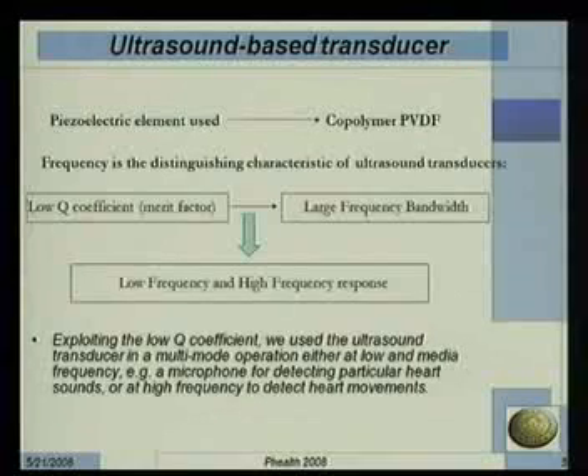The first system, the ultrasound-based transducer, is comprised of a piezoelectric element, which is a copolymer PVDF. This piezoelectric element has a low Q coefficient, which implies a large frequency bandwidth, and this allows us to use this transducer at low and high frequency response. At low frequency investigation, we can use this transducer as a simple microphone for detecting specific heart sounds, and at high frequency we use this transducer to detect the heart wall motion, heart wall movement.